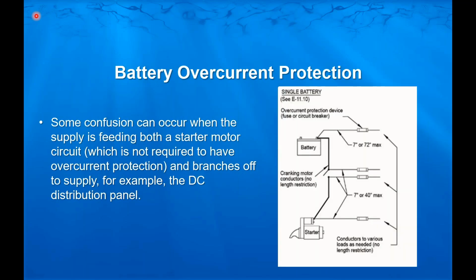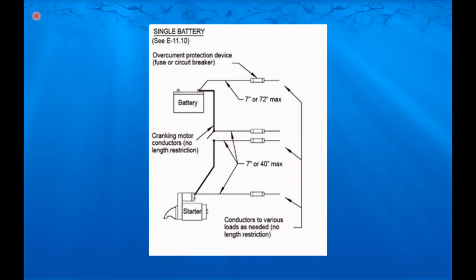There is some confusion that can occur when your power supply is feeding both a starter motor circuit, which is not required to have overcurrent protection, and it branches off to supply the DC panel or other things. So in our drawing here, which is the same as the other, you can see this circuit, the heavy black wire circuit, is our cranking circuit and does not need overcurrent protection. And if you put overcurrent protection in there, trying to protect this, it's going to trip every time you start the engine. So in this case, you're allowed to use the battery switch connection as your source of power to feed.